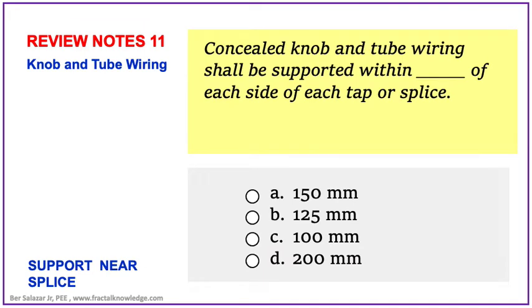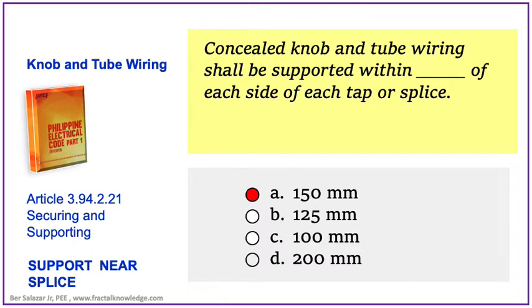Another possible problem asks: concealed knob and tube wiring shall be supported within blank of each side of each tap or splice. What is the support distance? The answer can be found in 2017 PEC Article 3.94, page 274, specifically section 3.94.2.21 Securing and Supporting. The keyword is 'support each side of each tap or splice.' The answer is letter A: 150 mm. Each knob tube wiring shall be supported.